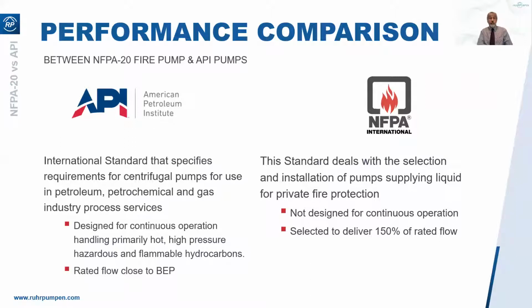Now, as I mentioned earlier, you guys are likely to ask us to comply with your client specs, which are going to be API 610 based. Really, API 610 is inappropriate for these services. It's a spec that's designed for handling hot, high pressure, hazardous, flammable hydrocarbons on a continuous basis and operating at or close to BEP, best efficiency point. Fire pumps, on the other hand, are relatively low pressure water pumps designed for standby service, 1 hour a week, and selected to deliver 150% of the rated capacity. The two requirements are mutually exclusive. It's very difficult to select a pump at best efficiency point that will also run out to 150% of rated point.